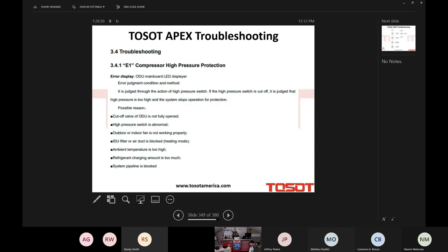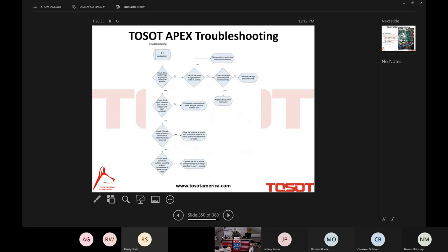There's your service manual, and there is an example of what you would find, the E1 high pressure. All of our diagnostic charts, all of the Tosot diagnostic charts, I love, are in this drop-down ladder chart. For me and for most people, it's just very easy to use. You're working like you would a ladder, from the top to bottom, going through voltage tests, going through resistance tests, probably changing a component somewhere along the way. But by the time you get to the bottom of the ladder, if all went according to plan, the system is up and running again.